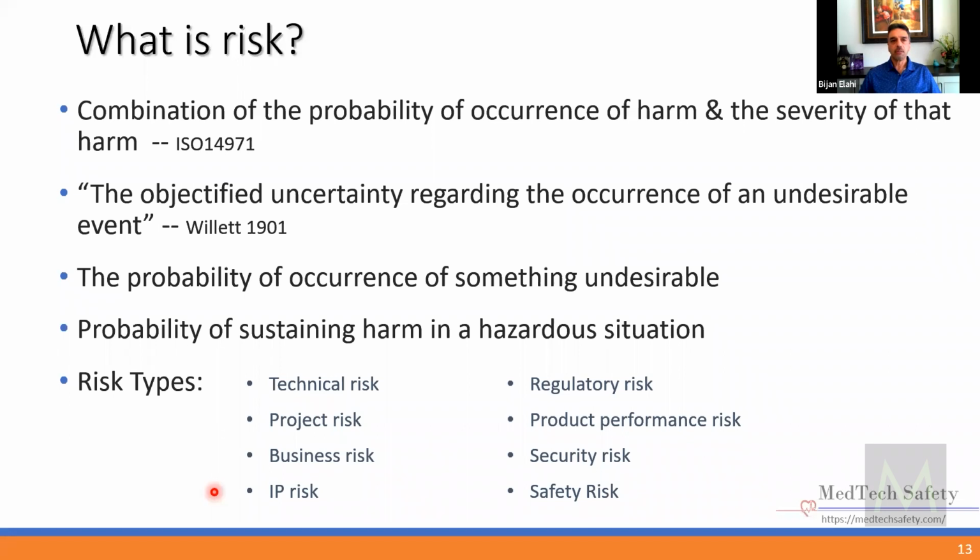When a business leader talks about risk management, they're thinking about business risk. For example, we are developing a new product. What are the chances of losing money on this product? We're trying to make money. In ISO 14971, we only talk about one kind of risk, and that's safety risk. And in fact, safety risk comes in 2 flavors itself: risks to patients and users from the use of a medical device. And there's another kind of risk, we call it EHS in America. It stands for environmental health and safety. And this is also what OSHA cares about. It's the kind of risk that can be to your health, but not from the use of a medical device. Like if you slip and fall down, that would be that kind of risk.